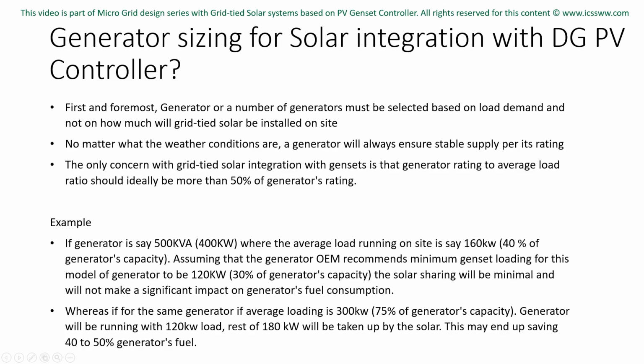Whereas, for the same generator, if the average load is 300 kilowatt, which is 75% of generator's capacity, the generator will be running with 120 kilowatt load. The rest of 180 kilowatt will be taken up by the solar. This may end up saving 40 to 50% of generator's fuel.